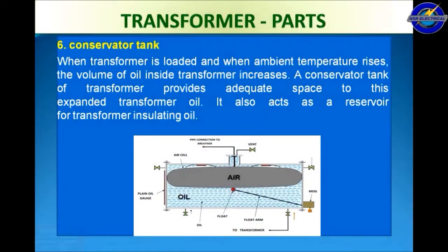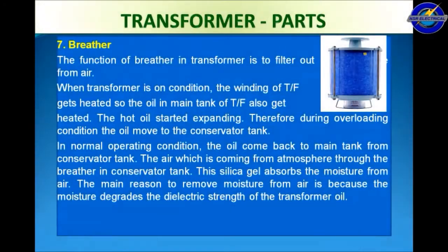Sixth one is conservator tank. When the transformer is loaded and when ambient temperature rises, the volume of oil inside the transformer increases. A conservator tank of a transformer provides adequate space for this expanded transformer oil. It also acts as a reservoir for transformer insulating oil.